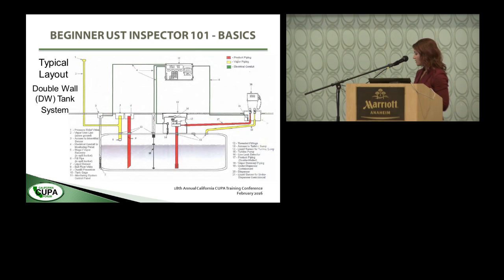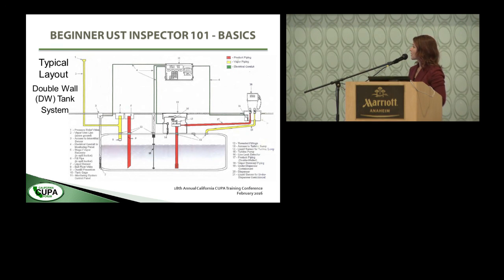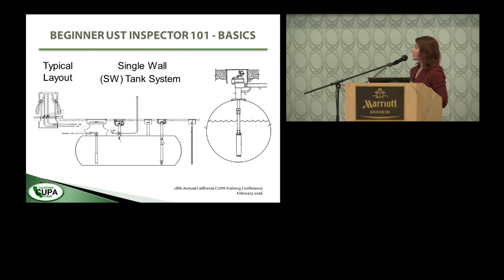This is a diagram of a typical double-wall tank. You've got the primary containment and secondary containment — the two tank shells — with interstitial space or annular space between them (interchangeable terms) and a sensor within that interstitial space. The yellow piping depicts vapor piping, so this would be a vent — all tanks need to be vented. The red depicts product — this is the fill tube where fuel or product enters the tank. There's a tank gauging probe connected to a monitoring console. The tank sump has the product piping and pump, where product is dispensed from the tank and drawn to the dispenser. A single-wall tank is not much different — it just has a single shell, so no interstitial or annular space.